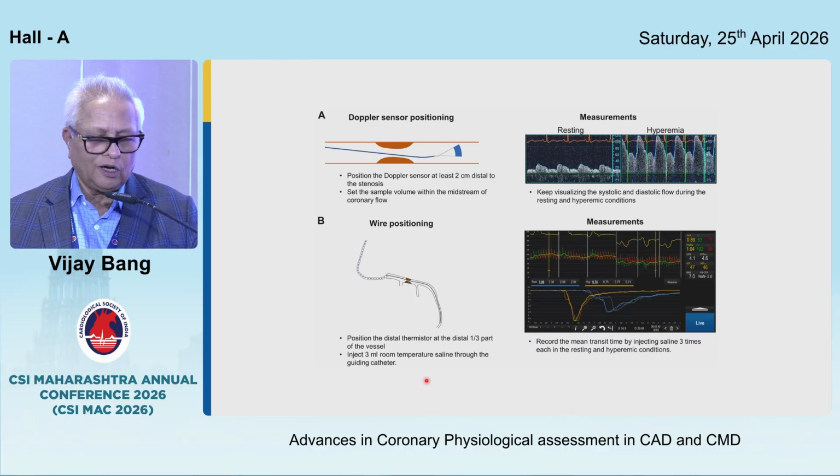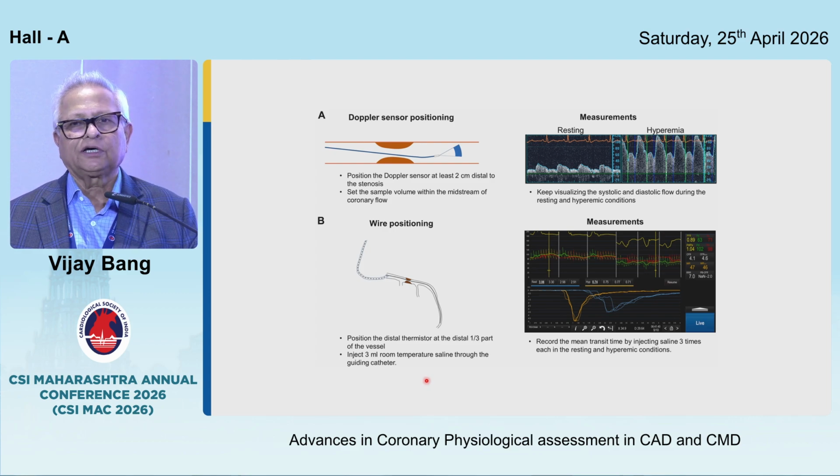Now, coming to how we test the CFR and IMR on CoroFlow, we just inject saline, and there are thermistors, proximal and distal thermistor.